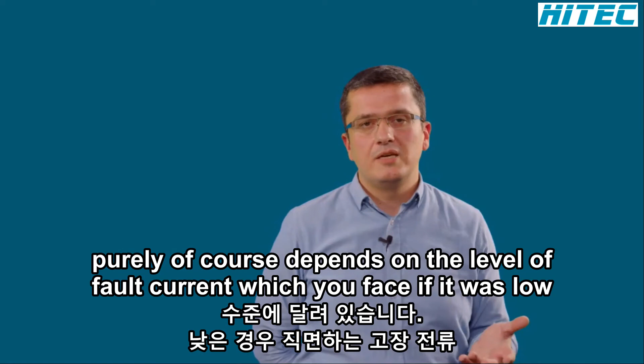Coming back to the question of whether the flaps need to be replaced or not, this purely depends on the level of fault current you face. If it was low, there may be no need. If it's too high, at the edge, the flaps may open up, but you may simply shift this replacement activity to the next planned maintenance activity. So no need to wait for closing or replacing the flaps in order to re-energize your switchgear.